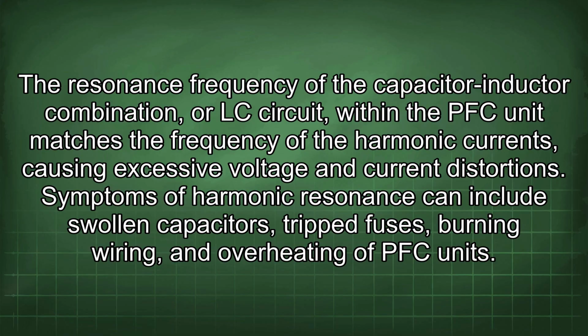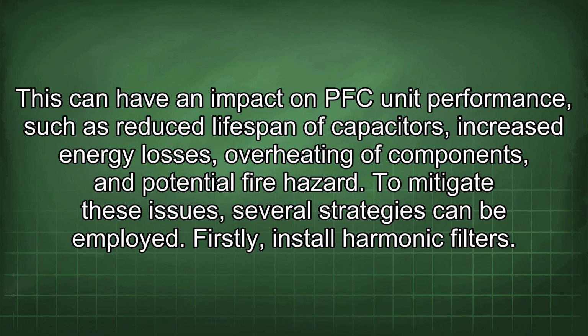Symptoms of harmonic resonance can include swollen capacitors, tripped fuses, burning wiring, and overheating of PFC units. This can have an impact on PFC unit performance, such as reduced lifespan of capacitors, increased energy losses, overheating of components, and potential fire hazard. To mitigate these issues, several strategies can be employed.